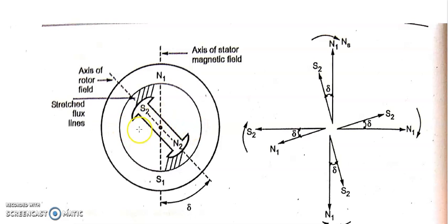It has the capacity to maintain synchronism till delta equals 90 degrees. After that, the motor will lose synchronism, come out of synchronism, and stop. So it is better to maintain delta less than 90 degrees, or even better at 88 or 89 or something in decimals, so that delta never reaches 90 degrees. Why? Because the force of attraction shown by the magnetic lines is going to weaken and weaken as you increase the load.